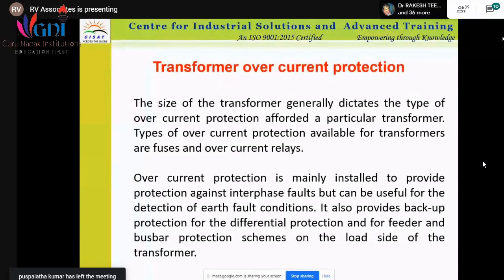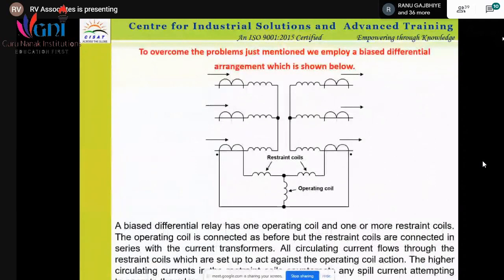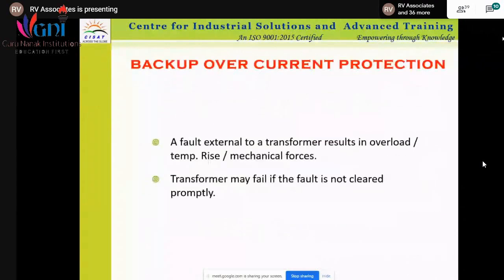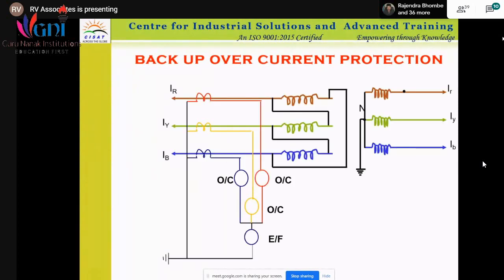Relay coordination means there is primary protection, then there is backup protection. First, the protection has to be done by the primary protection because it is a selective protection. Otherwise, your complete protection system will fail. If there is a transformer failure in some area, there are various grids in the substations, so only that particular failed area is to be tripped by the primary protection. If it fails, then it will go to the backup protection. So there is a gradation, and that is called relay coordination. Backup protection works only when there is a failure in the primary protection.